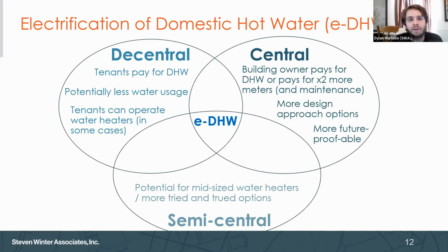With central systems, there are many different design approaches, and you can integrate them with your space heating and cooling systems in creative ways that utilize heat recovery, especially in summer when you need to produce hot water but, with a heat pump, end up producing cold air or cold water as a byproduct. You can use that to your advantage. As mentioned, central systems tend to be more future-proofable.